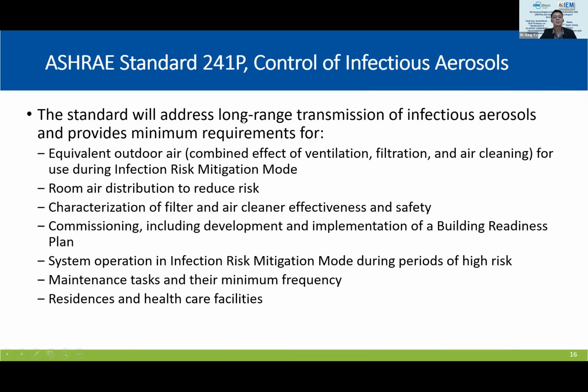For ASHRAE Standard 241P, the standard addresses the long-range transmission of infectious aerosol, and the minimum requirement here is for equivalent outdoor air for use during the infection risk mitigation mode. So now we are not simply talking about outdoor air, but equivalent outdoor air—because if we just drag in a huge amount of outdoor air, that will impact the energy consumption of the building.